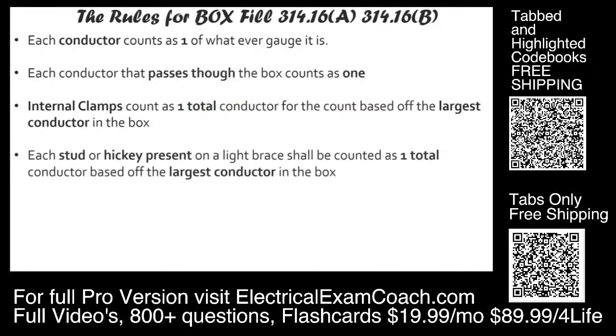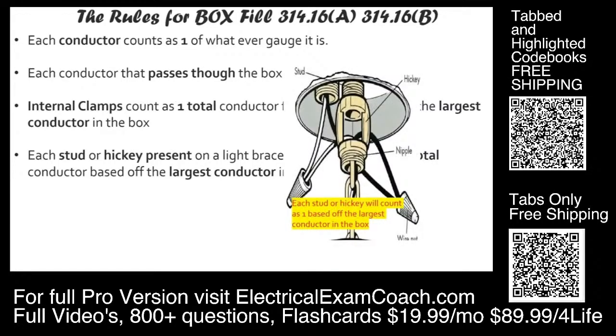Next, each stud or hickey that is present in the box shall count as one total based off the largest conductor that's in the box. Now, these are really old words, probably from the 30s if I had to imagine, but they still use them on examinations today. And this is what we're talking about.